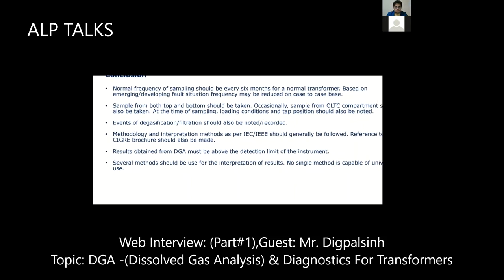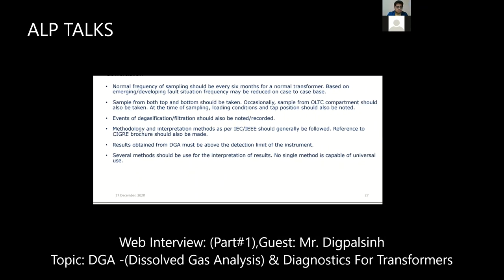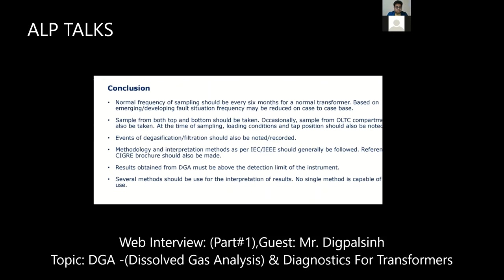And events of degasification, it is useful for the transformer, it is late. Then there are a number of interpretation methods, like IEC, IEEE, ABB, KEMA, Rogers. All have developed their own methods. So we should not rely on one particular method. If your gases are beyond the defined limit, hydrogen more than 200, acetylene more than 2 or 10, then you go with IEC analysis, then Duval analysis, then Rogers method, and come to a result.